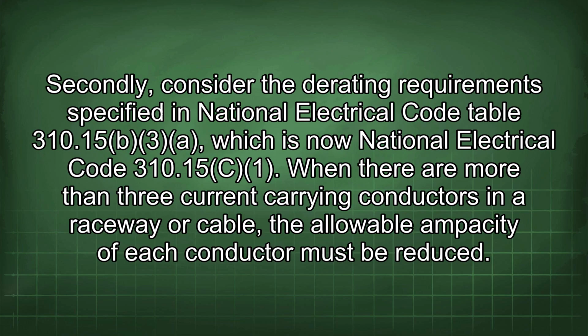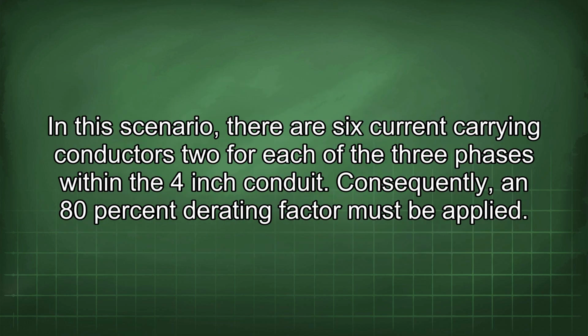Secondly, consider the derating requirements specified in National Electrical Code Table 310.15(B)(3)(a), which is now National Electrical Code 310.15(C)(1). When there are more than 3 current-carrying conductors in a raceway or cable, the allowable ampacity of each conductor must be reduced. In this scenario, there are 6 current-carrying conductors, 2 for each of the 3 phases within the 4-inch conduit. Consequently, an 80% derating factor must be applied.